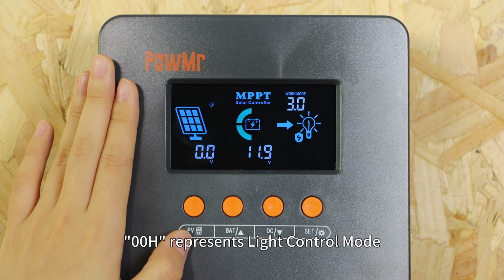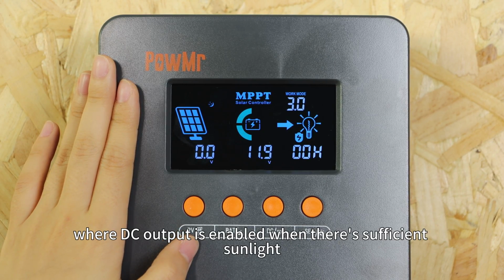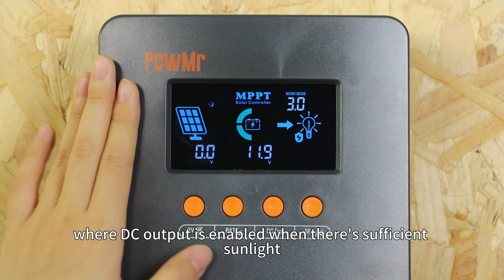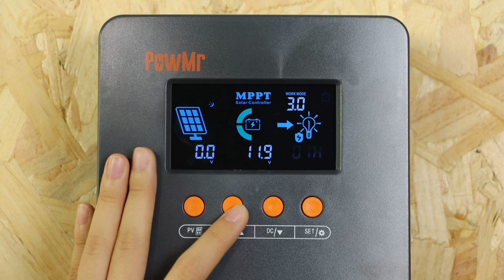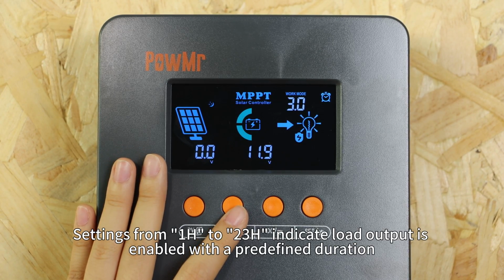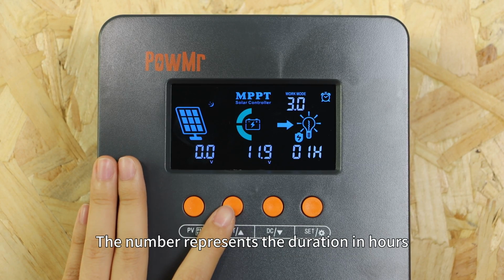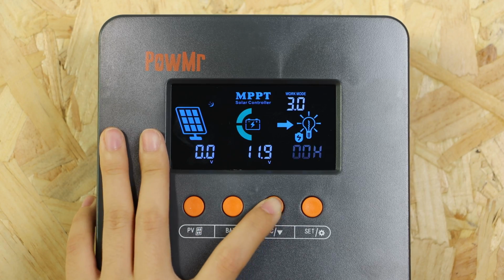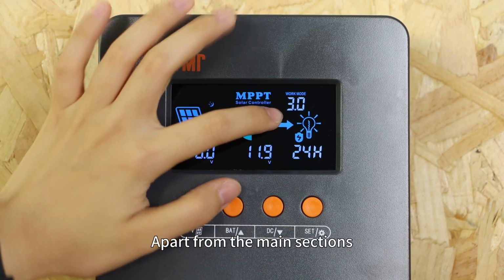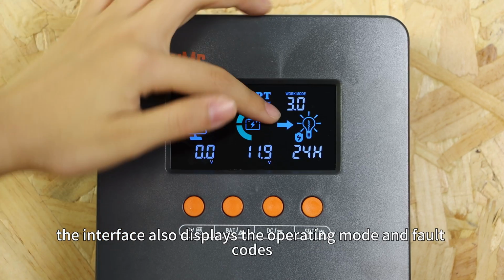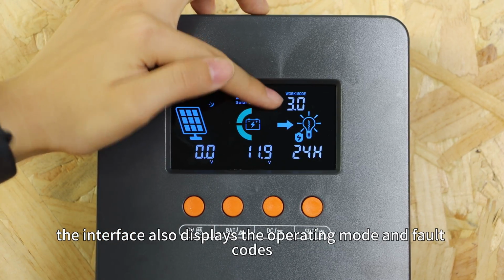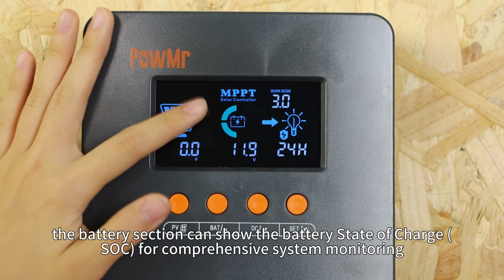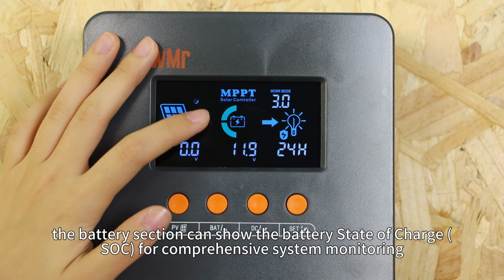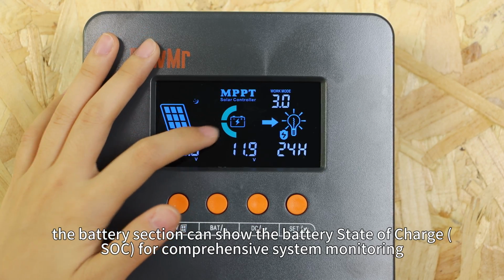00H represents the Light Control Mode, where DC output is enabled when there is sufficient sunlight. Settings from 1H to 23H indicate that load output is enabled for a predefined duration. The number represents the duration in hours. Apart from the main sections, the interface also displays the operating mode and the fault code. Additionally, the battery section can show the battery state of charge for comprehensive system monitoring.